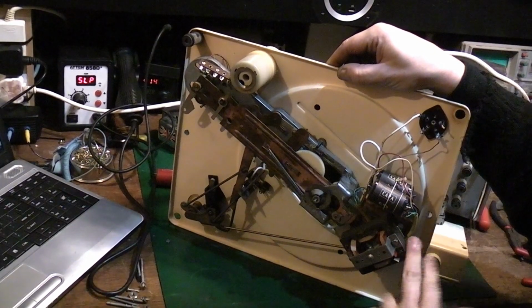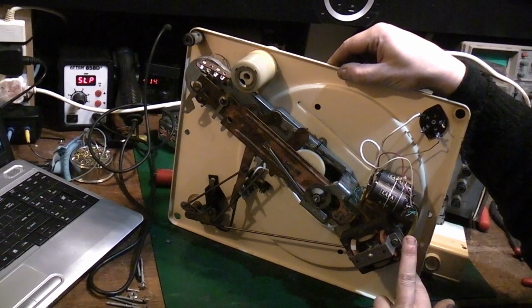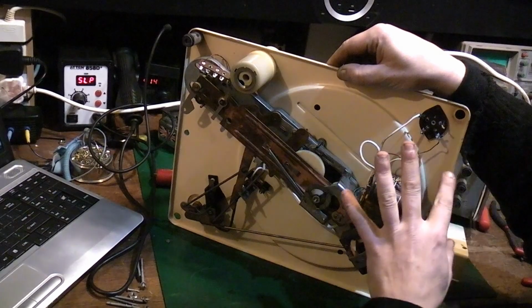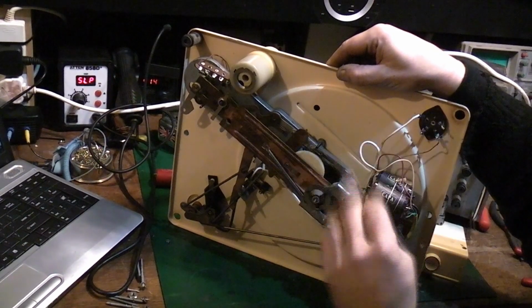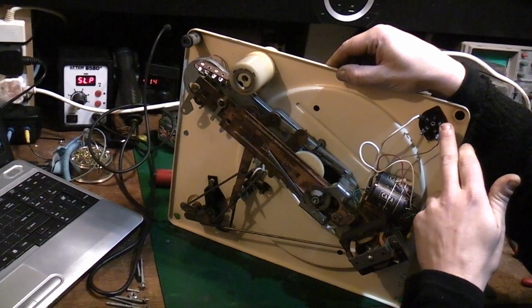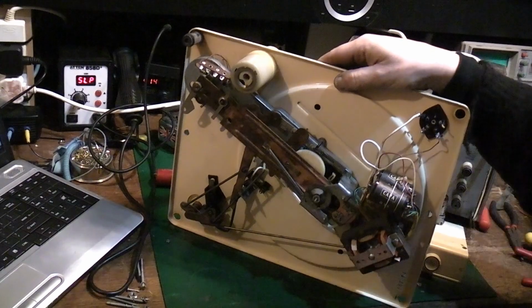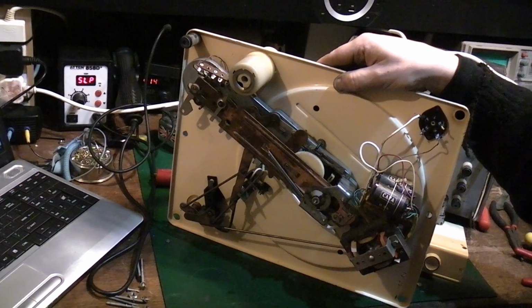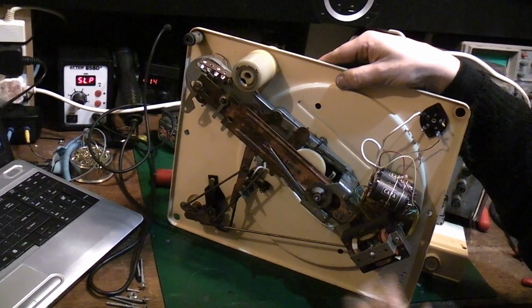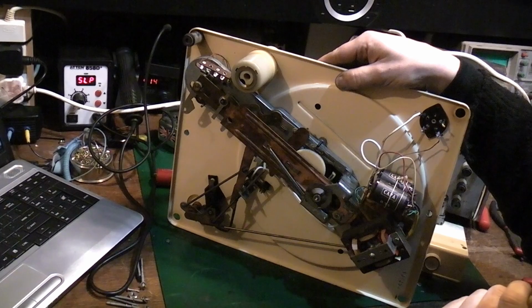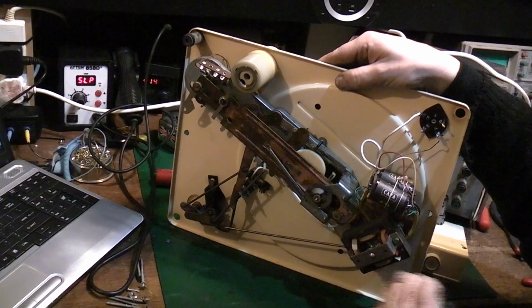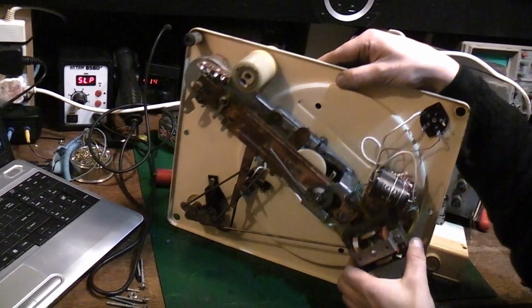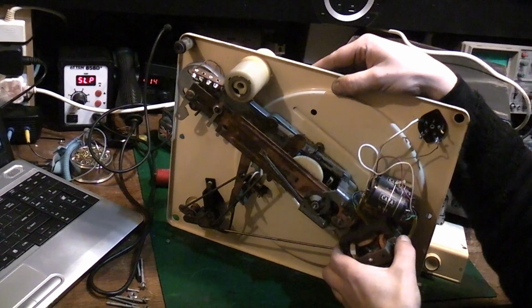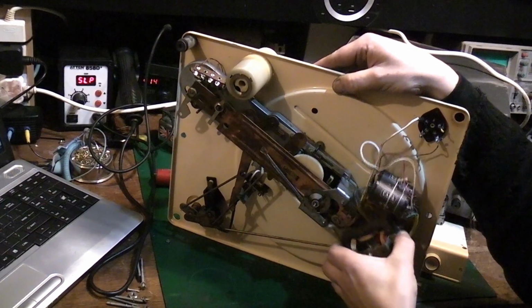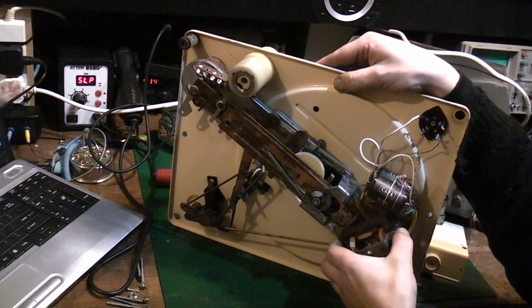Looking at how this is wired, I have a feeling this might be a 110 volt motor, using another secondary wired somewhere through that transformer, so even with 230 or 240 volts coming in, the motor's probably still running at 110-115 volts. We can still do that with the new transformer because of how the primary is wired - we could probably take a tapping off and run it like that. But that's concerning me, I'll have to do something about it, because it's not going to play properly with worn bushings that should be hard to move. So yeah, that's a project in itself.